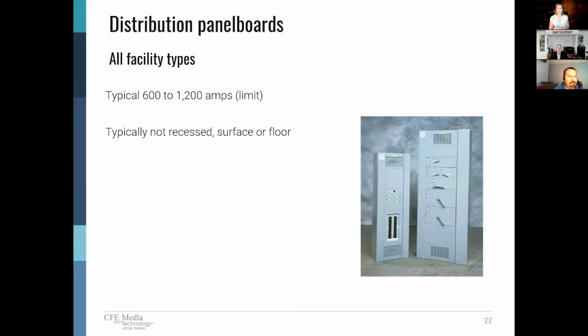Next slide. So now we're going up in size, and what used to be called, and what I still categorize, as distribution panel boards. These are typically from 600 to 1200 amps. They're going to feed large mechanical equipment. They would probably feed other branch panels, lighting and receptacle branch panels. These are typically not recessed in a wall. They're surface mounted, they're deeper, they're bigger, they sometimes sit on the floor.